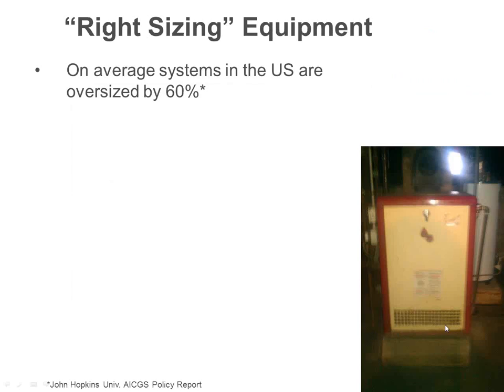What does most people do? Well, add safety factors. Really think about how a boiler gets sized originally. An engineer, contractor, whoever is in charge of it, this goes back 30, 40 years, did a heat loss calculation. Once they did that heat loss calculation, they specified a certain boiler, and they picked the size. Well, this is how things started getting out of control. The winning contractor then picked that boiler, goes to his favorite wholesaler, and the wholesaler says, hey, you need a 250? I got 300s, and they're less than 250, and I got a big sale on them. I bought too many. So now immediately that boiler just became 50,000 BTUs bigger than was actually necessary.